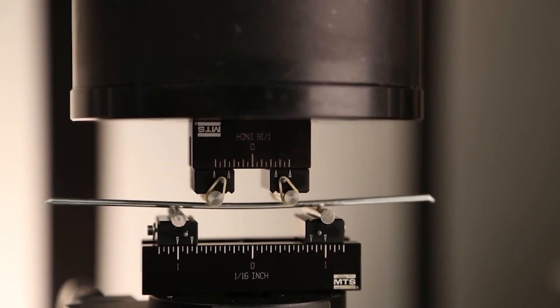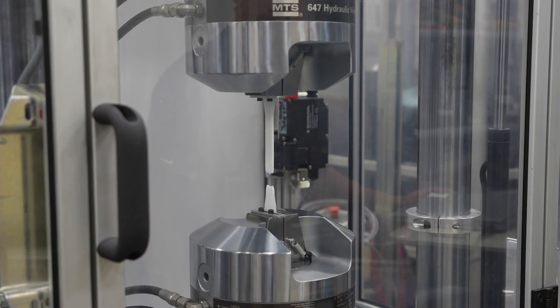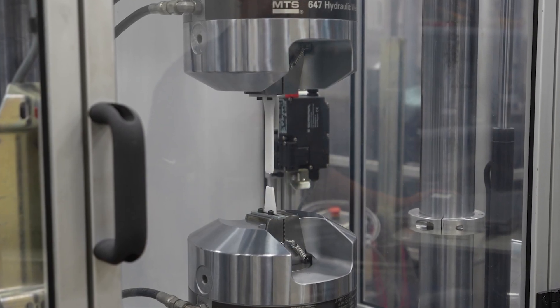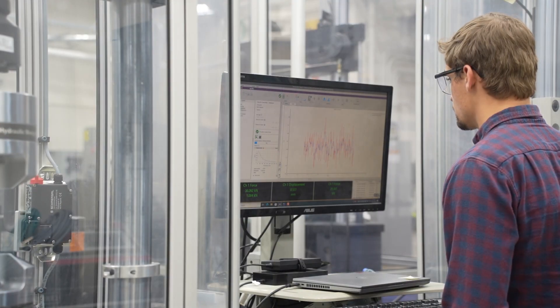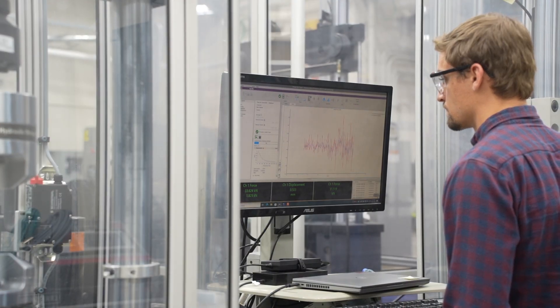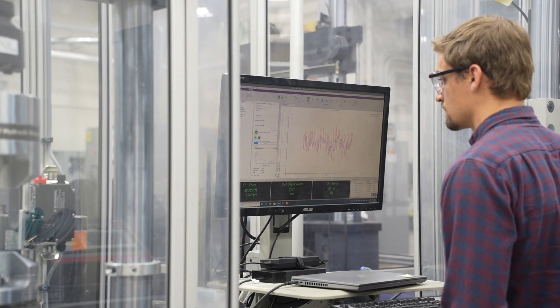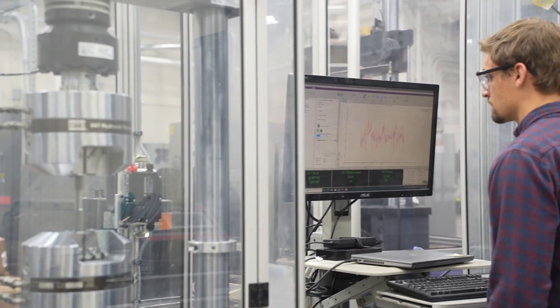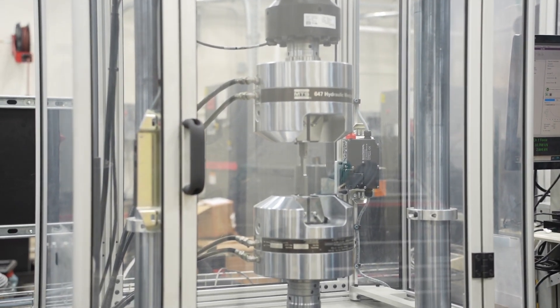Test system tuning is important as different types of specimens may react differently to certain loading conditions. If the system is not tuned properly, test results could be compromised because the system might not reach the desired load or displacement values.